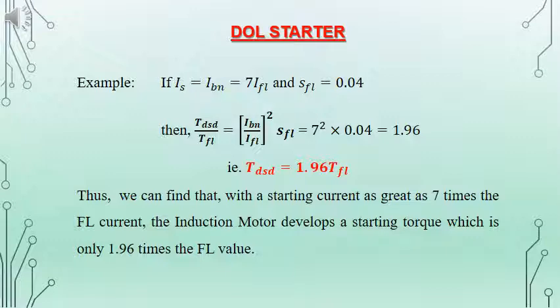By solving the equation we get TDSD is equal to 1.96 TFL. Here we can see if we go for DOL starter, it will cause very high current, around 7 times that of the full load current, and it will be producing only 1.96 times that of the full load torque. There is a low starting torque condition in the case of DOL starter.